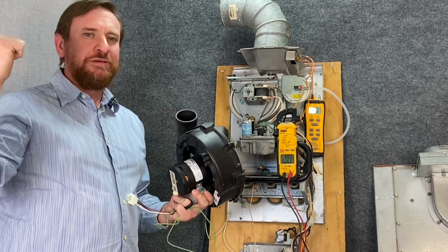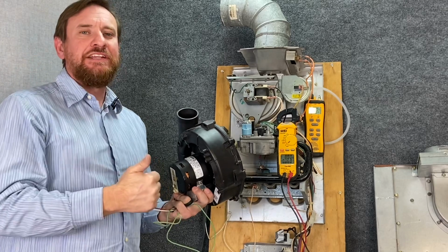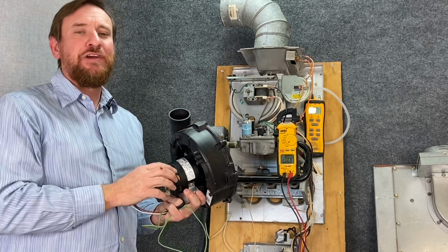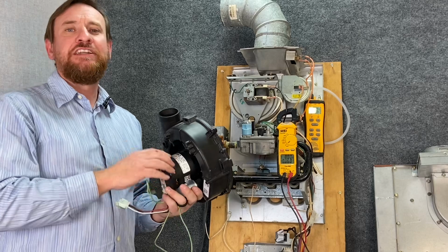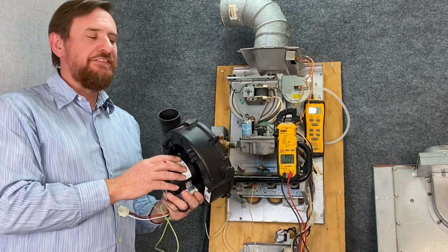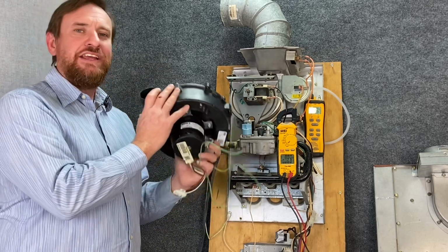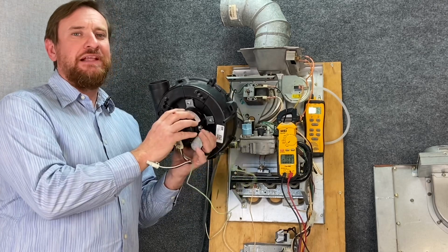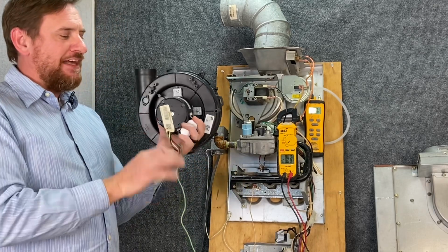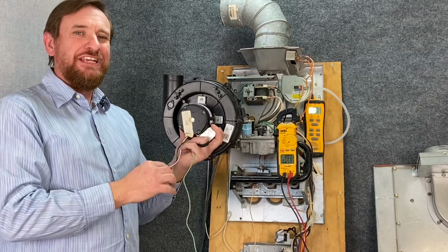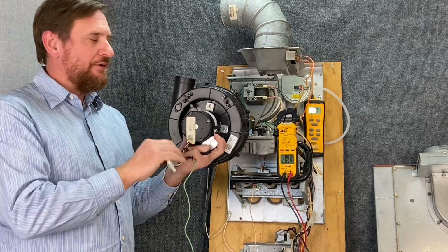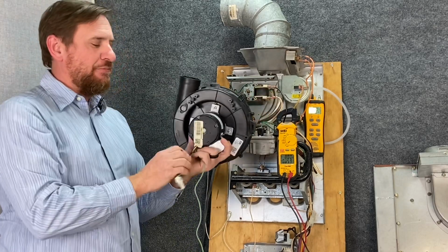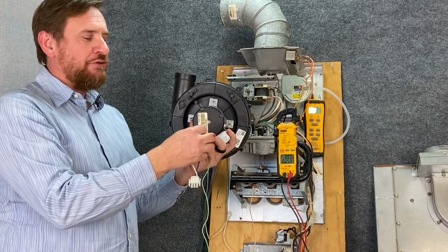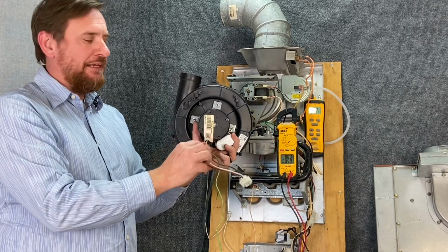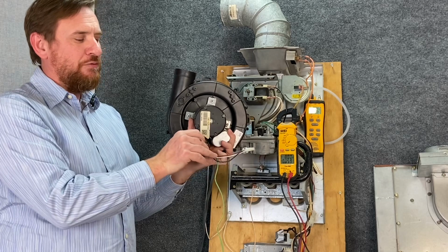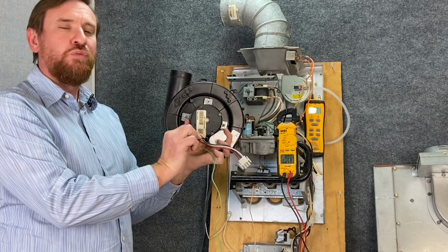The PVC runs completely outside. The PVC can handle the condensation, and it can handle the pressure without losing any carbon dioxide or any combustion gases into the house or the living space. So a Category 4 will have this plastic style vent pipe. On top of that, this particular motor is unique because it's a 2-speed motor. Instead of having 2 wires going to this motor, we actually have 3. So we're going to use black and common for high speed, or we use red and white, which is common for low speed. So we're going to use one at a time.